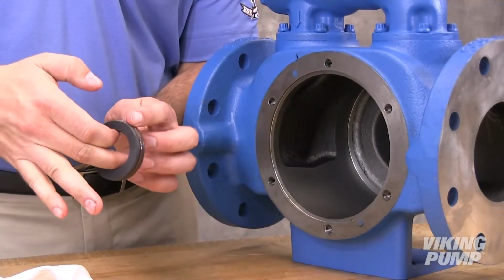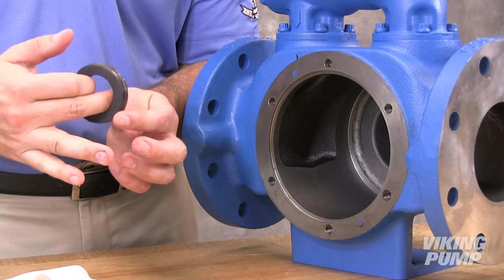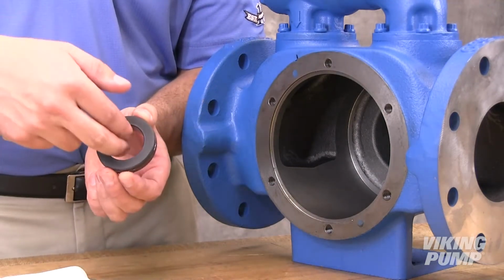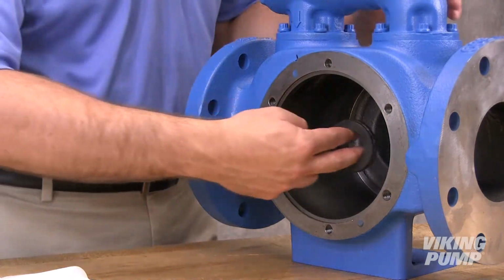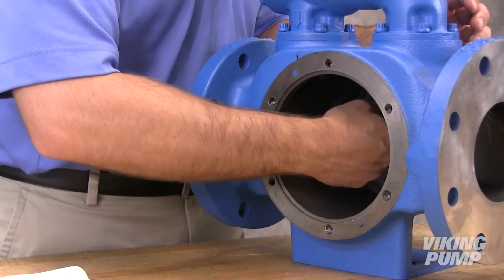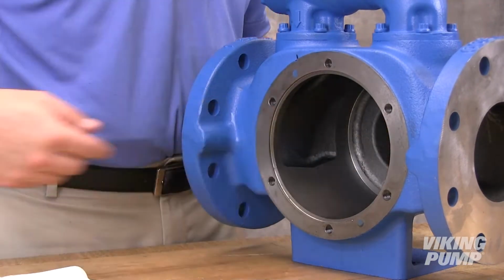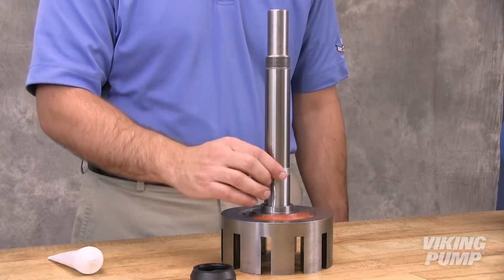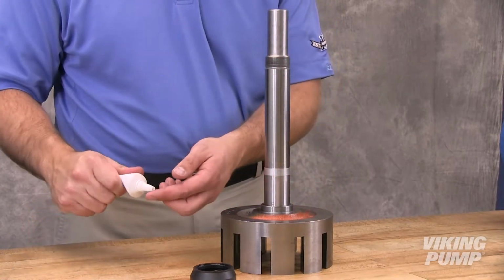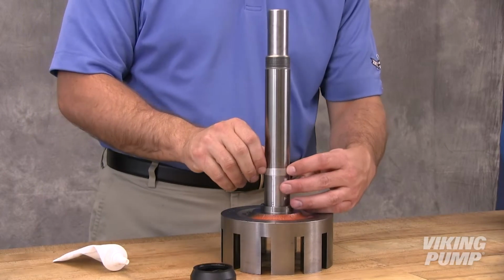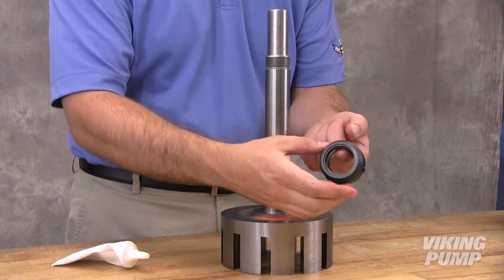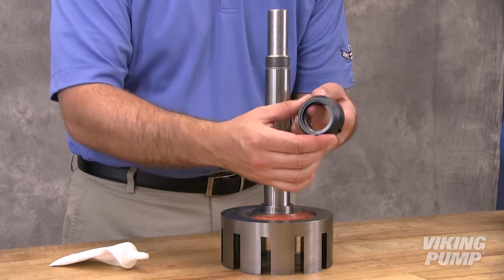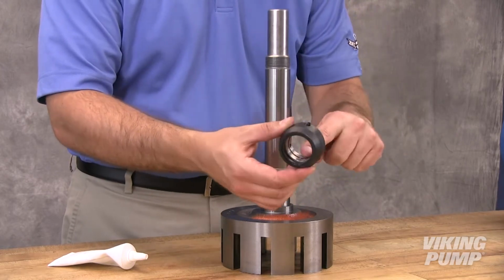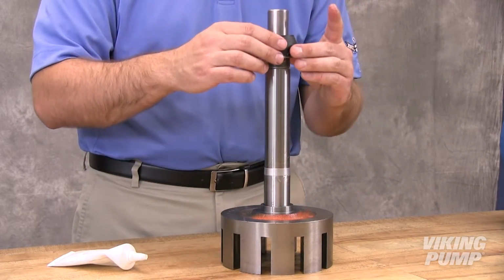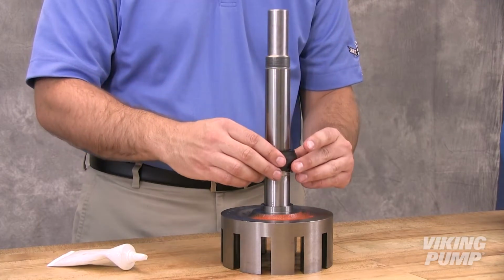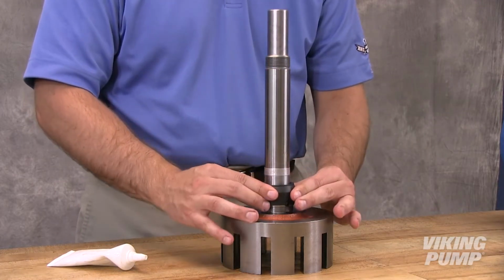Coat the outer diameter of the seal seat with a compatible O-ring lubricant. Then press the seal seat into the seal housing bore, ensuring that the unlapped face is fully seated in the bottom of the bore. Next, place the tapered installation sleeve on the shaft. Coat the sleeve and inner diameter of the seal rotary member with a generous amount of O-ring lubricant. Slide the seal with the lapped surface facing up and away from the rotor over the installation sleeve until it's just contacting the back of the rotor.